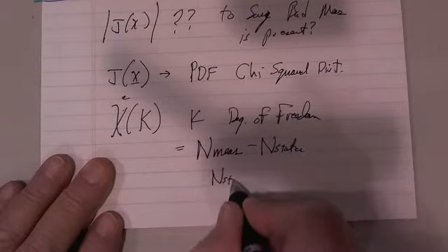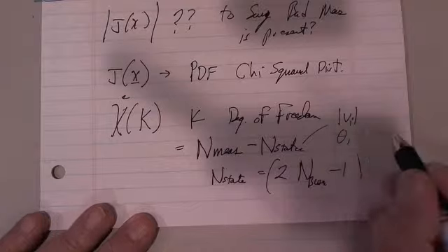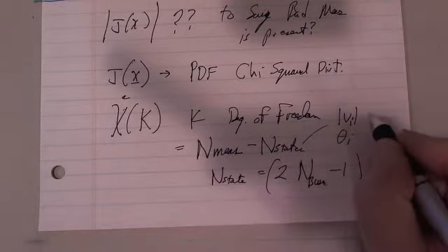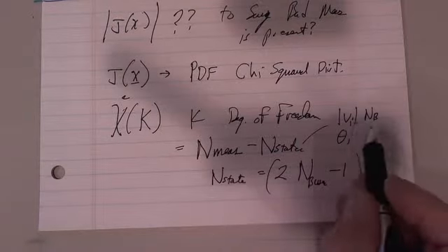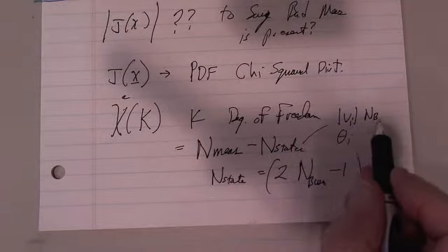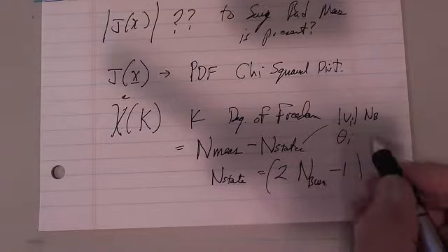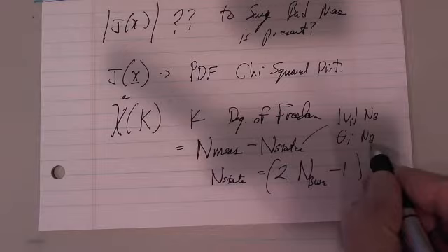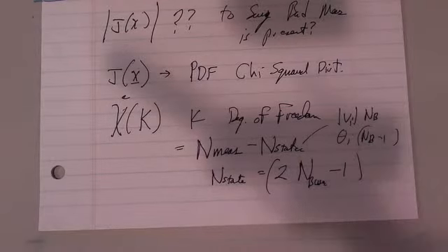The reason we end up with the minus 1 is that the states are the voltage magnitudes and the phase angles. We have NB voltage measurements, voltage magnitudes that we could measure. But for the phase angles, we have NB minus 1, because one of them we declare as 0 degrees. Then we're basically looking at the phase angles of all the other buses, and that's our reference or slack bus, whatever you want to call it.